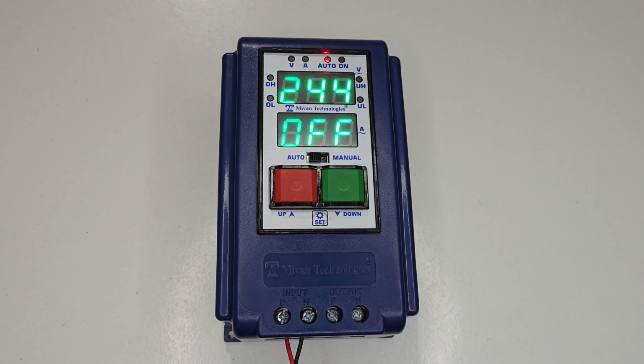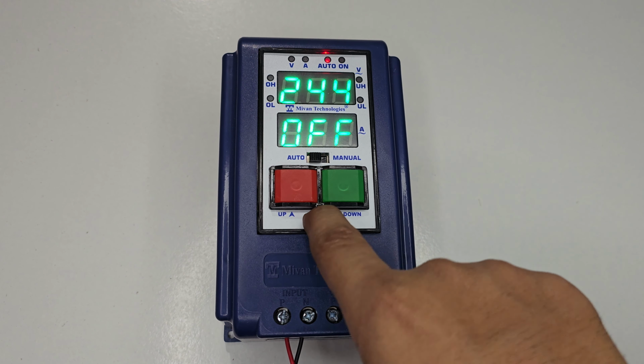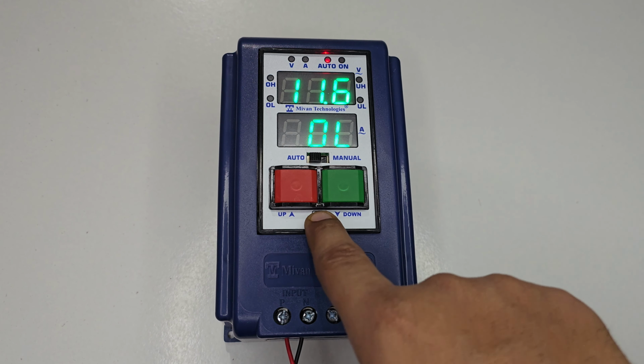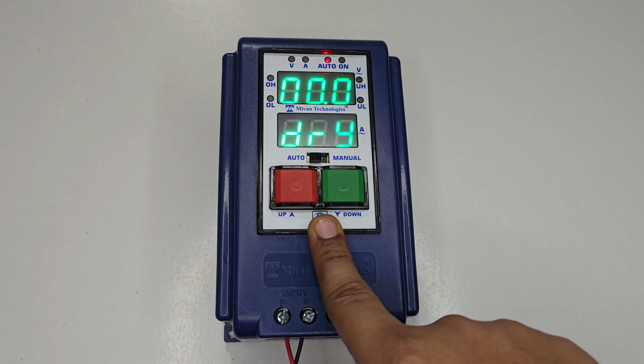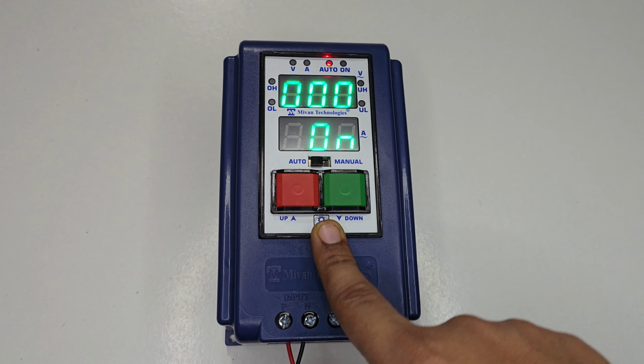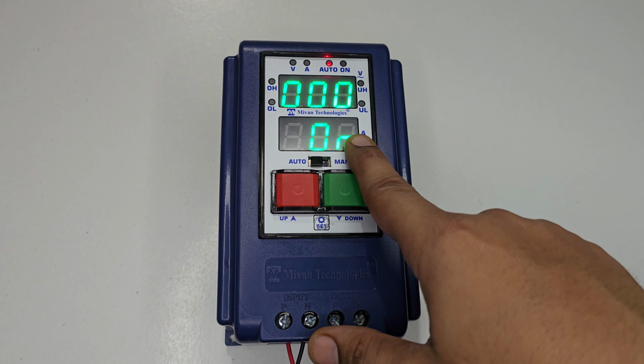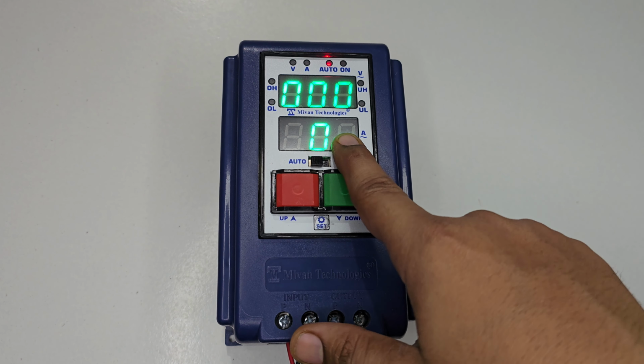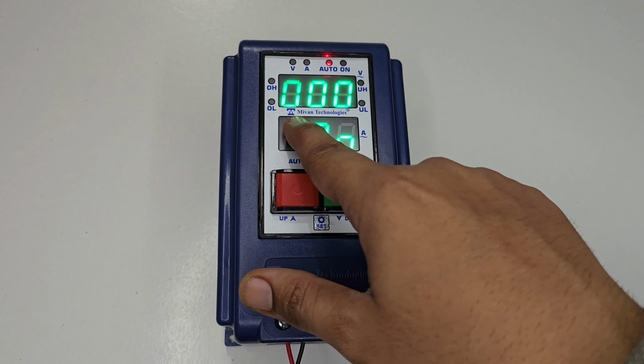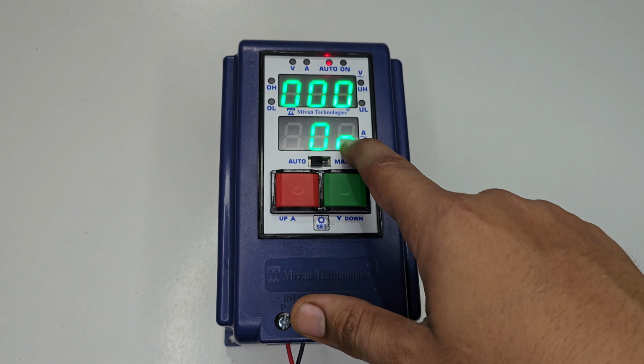When you enable a CYT or CYW mode, you can see a cyclic on and off timing setting in the main menu. So in the main menu, press the set button, you can see overload. Press the set button, you can see a dry. Press the set button, here you can see a cyclic on timing. The cyclic on timing is because we have enabled the CYW mode.